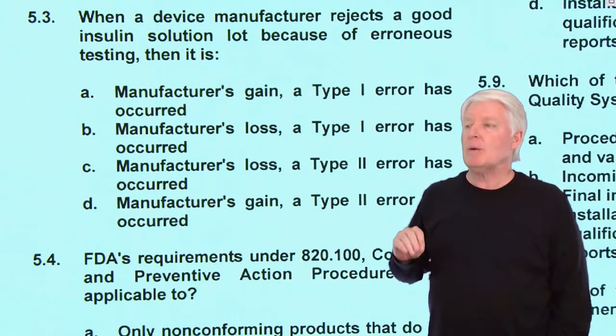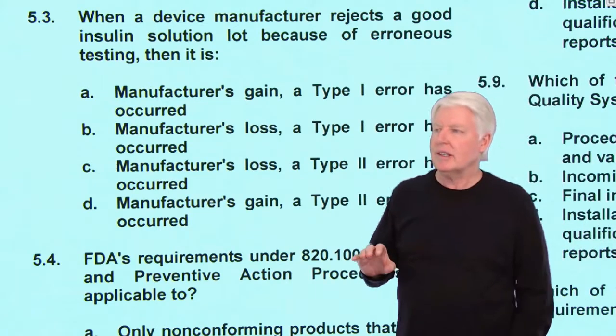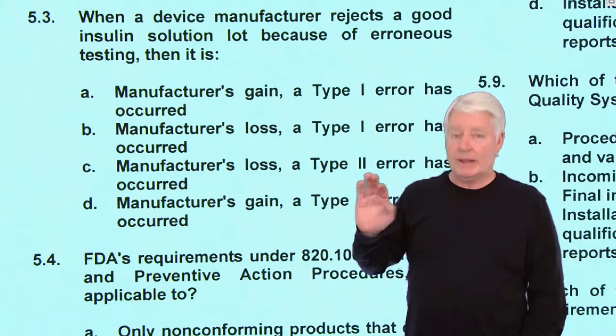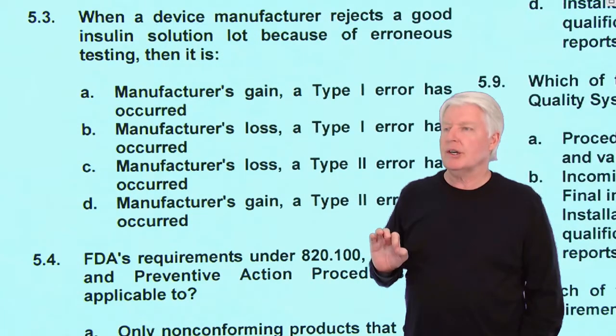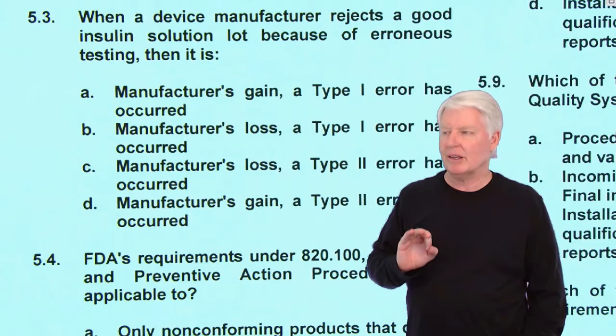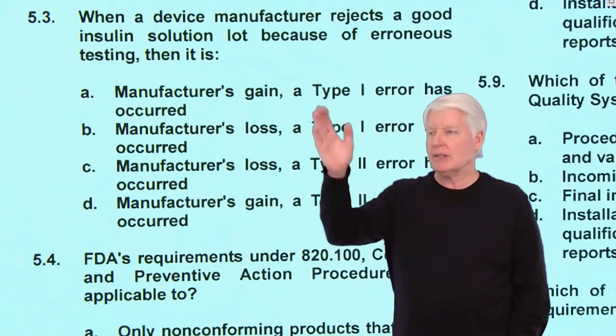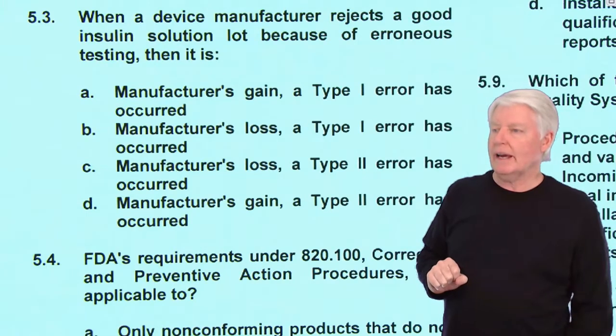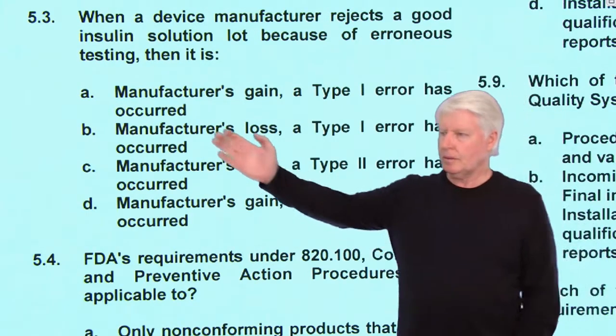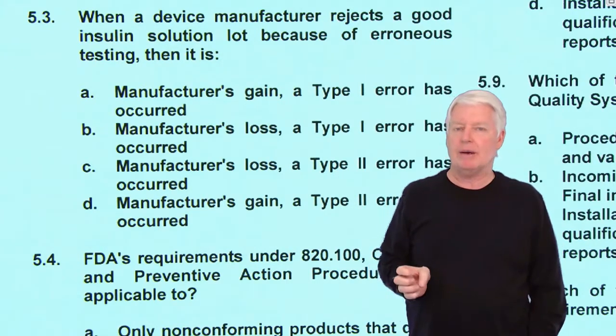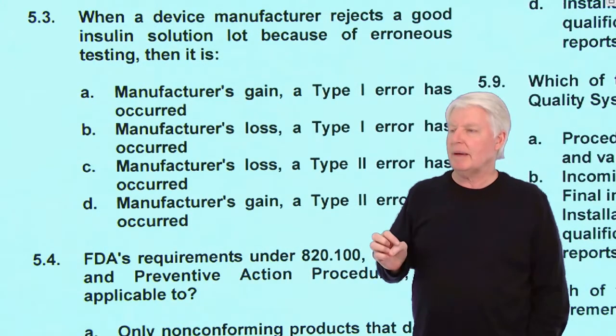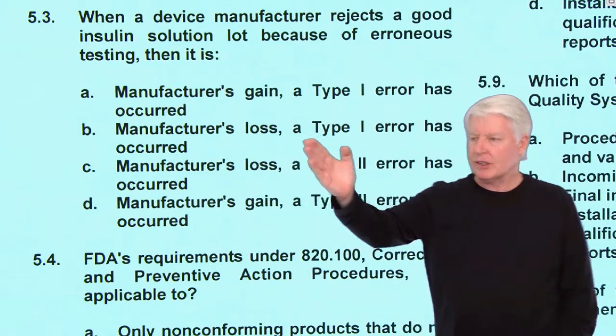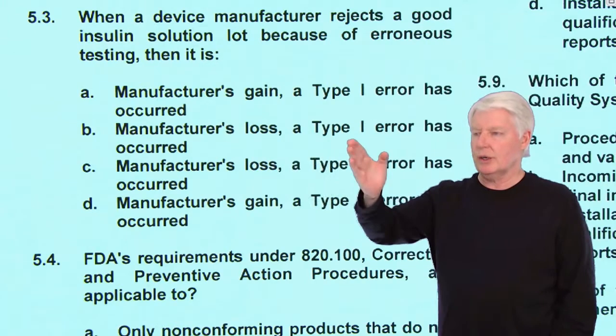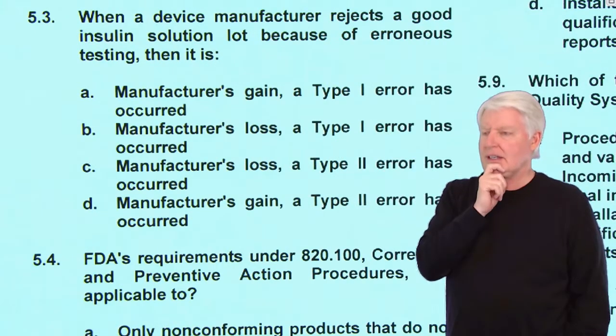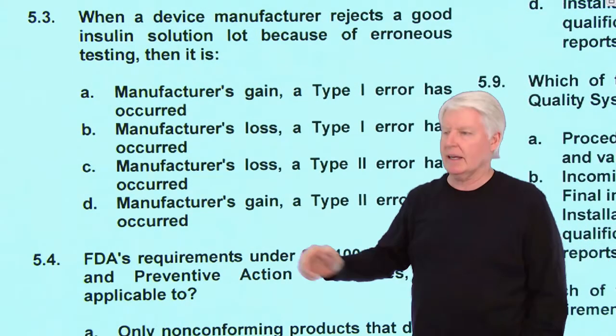Remember what beta is: beta risk would be stated this way, a device manufacturer accepts a bad insulin solution lot because of erroneous testing, that would be beta. But this one, the way it's read, has to be alpha risk. Manufacturer's gain? No, it's not a gain. Remember, they call it producer's risk, a manufacturer's loss. So there it is: manufacturer's loss, a type 1 error has occurred. This is true. They also call that producer's risk, and that's most of the terms for it. So B is the correct answer.